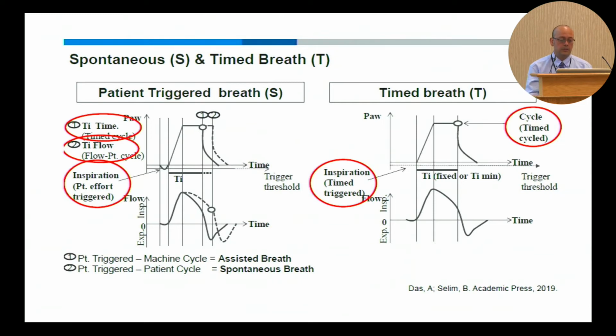And that's what ResMed does. So this would be a ResMed device, which from that point of view is simpler, because here all the breaths on AVAPS are time cycled. So if you put 1 minute of inspiratory time, all the breaths are going to cycle after 1 minute. So you see here it goes from EPAP to IPAP. Sorry, no, it's not 1 minute, it's 1 second. Then for 1 second, that breath is on inspiration. Once you reach 1 second, exhalation starts. And you see here the flow is the same. It doesn't change because the flow is constant and you're cycling by time.